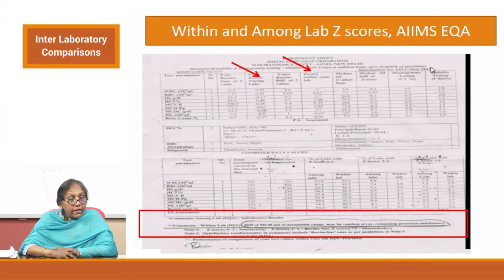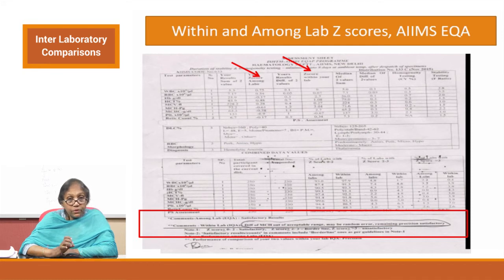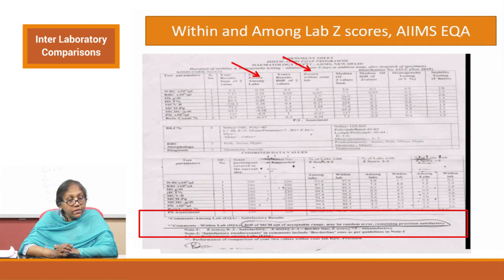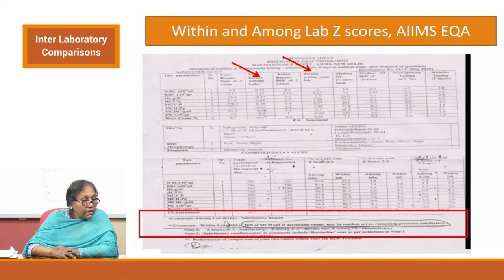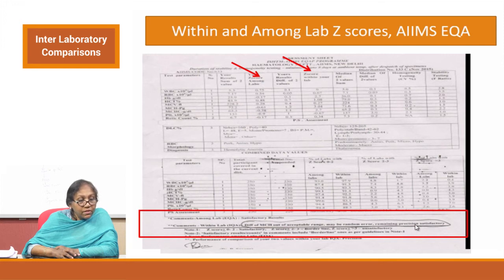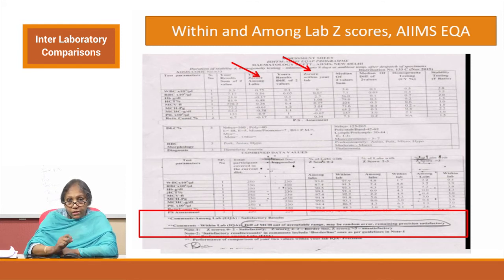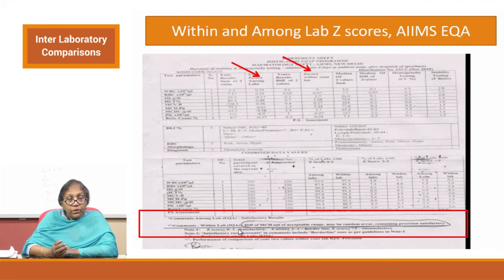This report is from the AIIMS EQAS program for CBC analysis. It provides a Z score among labs and a Z score within the lab — this particular EQAS asks for 2 or 3 runs, calculating the intra-run percentage difference. This gives you a comment on precision in addition to accuracy via Z score. The report comments: EQAS satisfactory results, while noting that the internal quality assurance difference of MCH is beyond the acceptance range and may be a random error; rest of precisions are satisfactory.